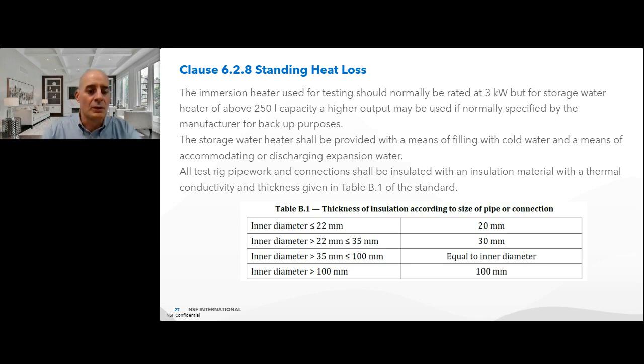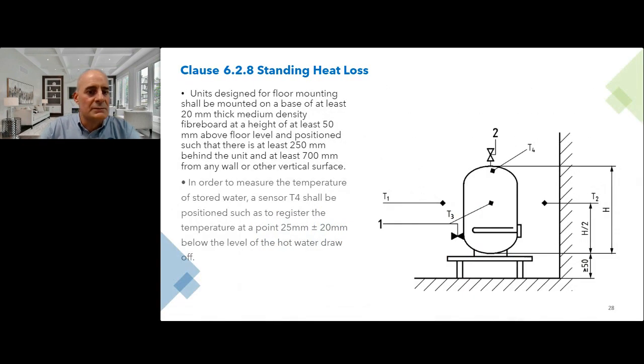So if the connection pipework is less than or equal to 22 mm, the thickness of the insulation needs to be 20 mm. For pipework greater than 22 and less than or equal to 35 millimeters, it's 30 mm, and so on, as listed in the table. Units designed for floor mounting should be mounted on a base of at least 20 millimeter thick medium density fiberboard at a height of at least 50 millimeters above floor level and positioned such that there is at least 250 millimeters behind the unit and at least 700 millimeters from any wall or other vertical surface.